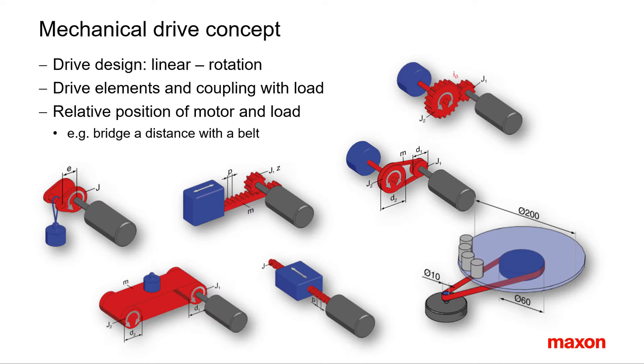The mechanical concept and bearing systems are also part of the motion output. Drive types adapt the output from motor or motor-gearhead to the needs of the load. Two different drive types can be distinguished: linear or translational drive types such as spindle drive, rack and pinion, and conveyor belt convert rotational motor motion into linear load motion; rotational drive types transmit a rotational movement to the load. A full mechanical description includes bearings and guidances capable of supporting all kinds of reaction forces, also important for estimating friction forces. The orientation with respect to gravity may also be valuable information.